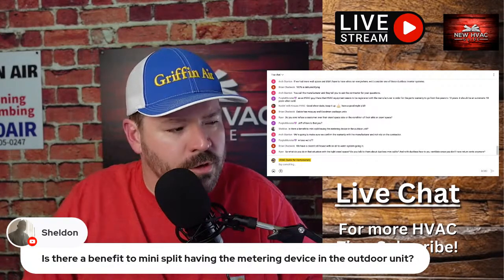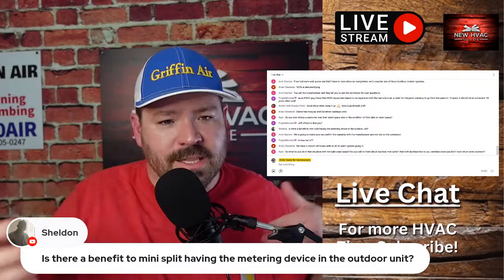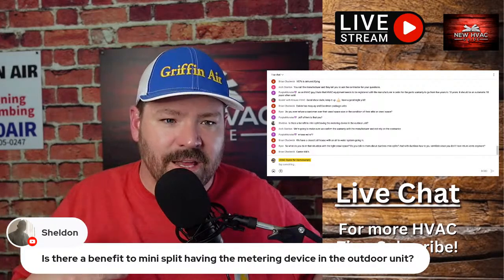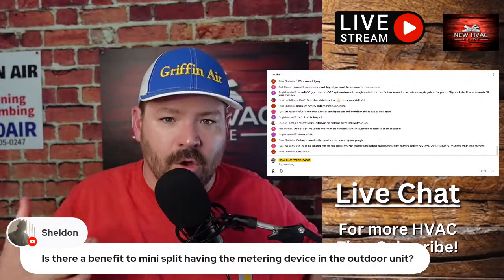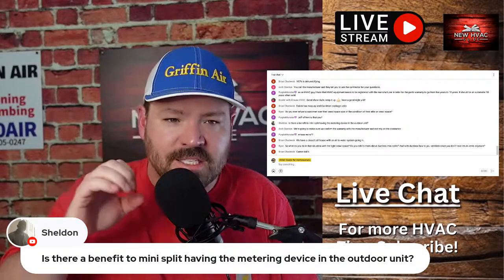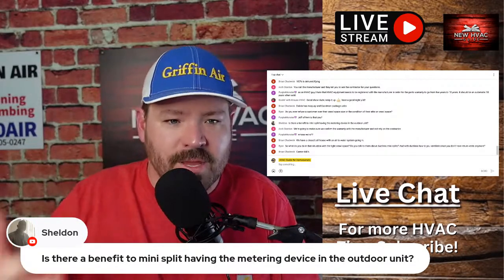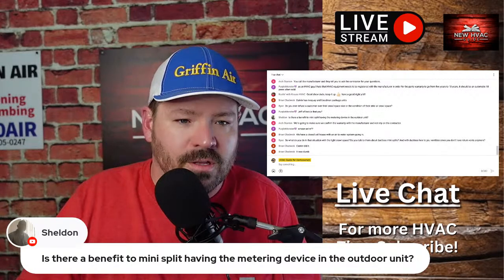If they had the metering device in the indoor unit, you wouldn't have to insulate the small line. You see mini splits have to insulate both lines, and that's because the metering device is in the outdoor unit.